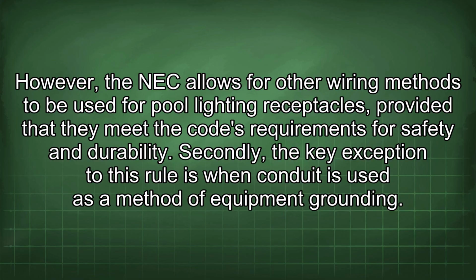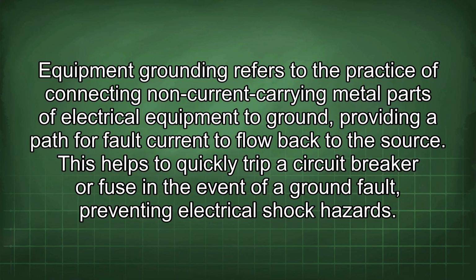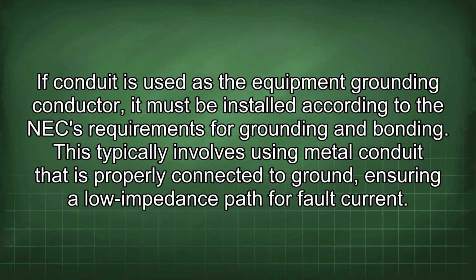Secondly, the key exception to this rule is when conduit is used as a method of equipment grounding. Equipment grounding refers to the practice of connecting non-current carrying metal parts of electrical equipment to ground, providing a path for fault current to flow back to the source. This helps to quickly trip a circuit breaker or fuse in the event of a ground fault, preventing electrical shock hazards. If conduit is used as the equipment grounding conductor, it must be installed according to the NEC requirements for grounding and bonding. This typically involves using metal conduit that is properly connected to ground, ensuring a low impedance path for fault current.